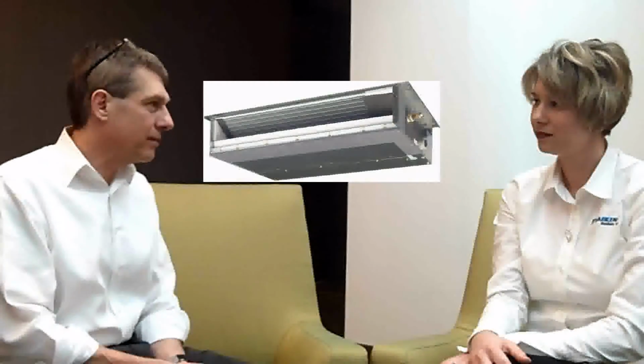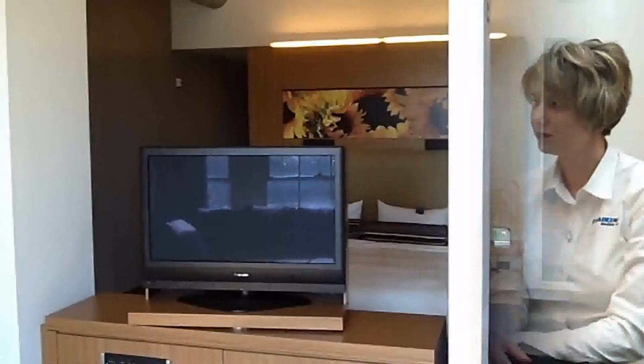Inside the guest room itself, for the location of the air handling units, we had limitations of existing slab height, which obviously couldn't be changed, and we decided to go ahead and locate the units above the guest bathroom ceiling, so there were considerations of maintaining the minimum height, leaving a relatively small space to fit the unit, and Daikin was able to provide a slimline unit that worked out perfectly.